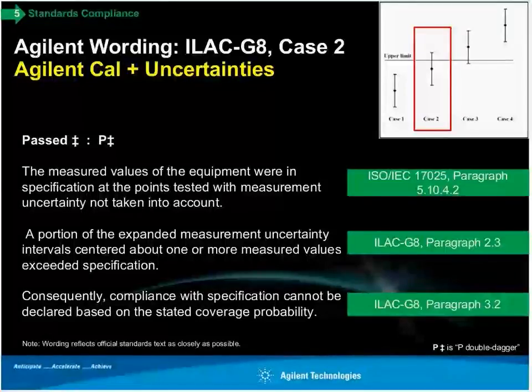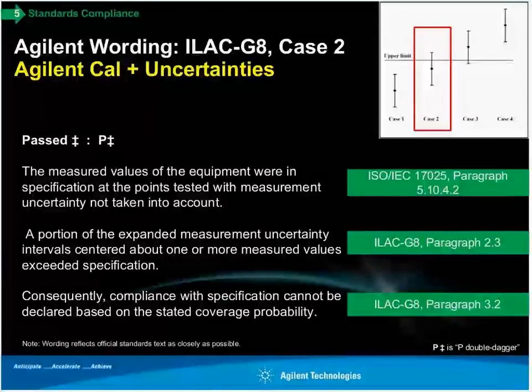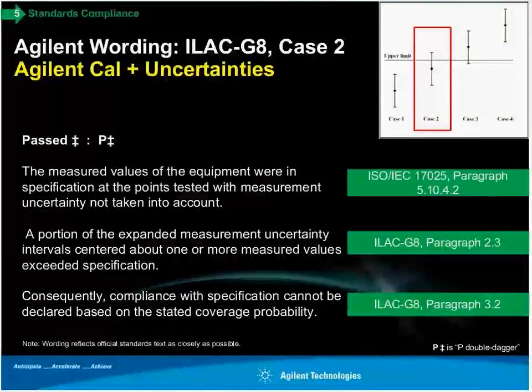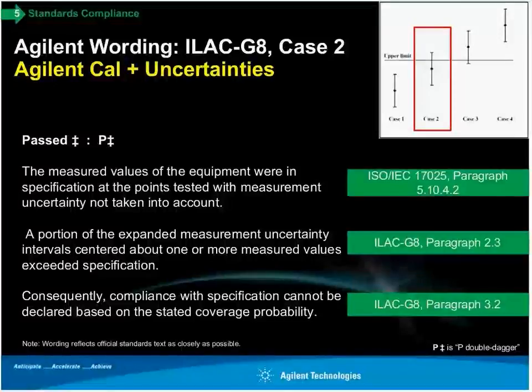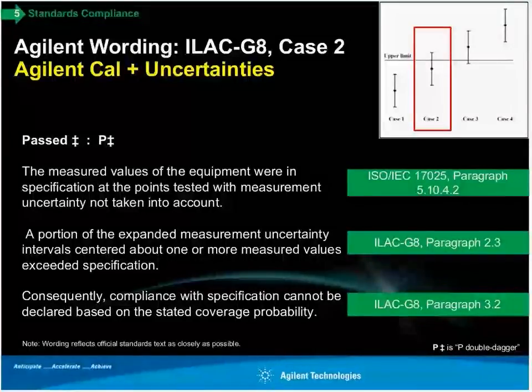on, and they're identifying this with a P double dagger. And when there is this case of case 2, there's a few different areas that we have to take a look at. First area is 17025 at 5.10.4.2. Here we've got the measured values of the equipment were in specification at the points tested, with the uncertainty not taken into account. So when we look at ILAC G8 and paragraph 2.3, a portion of the expanded measurement uncertainty intervals centered about one or more measured values exceeded the specification. Okay, so now with paragraph 3.2 in G8, consequently, compliance with the specification cannot be declared based on the stated coverage probability.